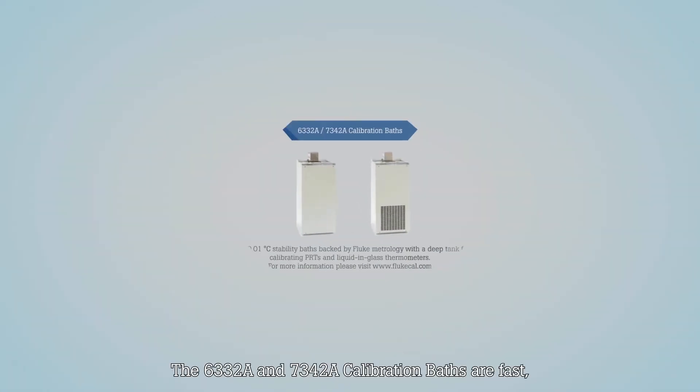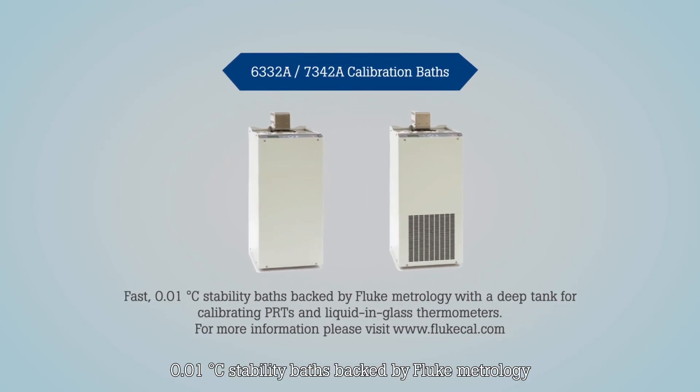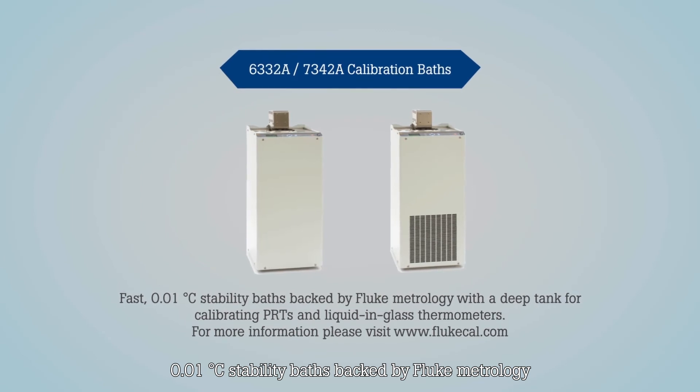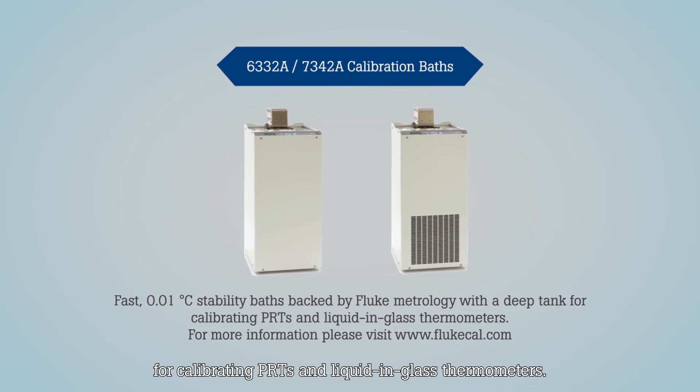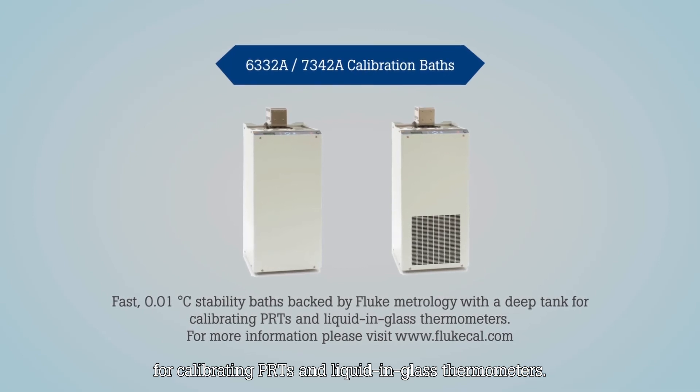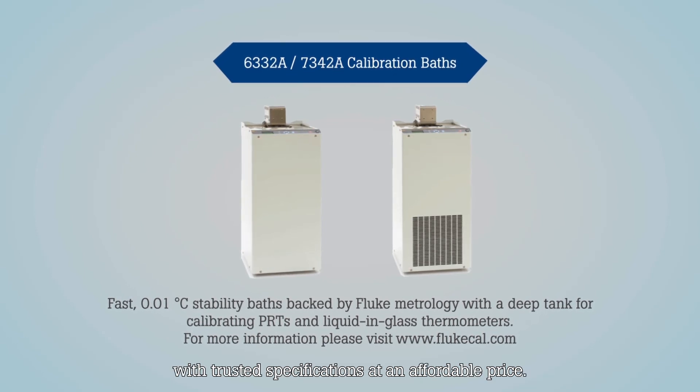The 6332 and 7342 calibration baths are fast 0.01 degree Celsius stability baths backed by Fluke Metrology for calibrating PRTs and liquid-in-glass thermometers. They're ideal for labs that need a high-quality bath with trusted specifications at an affordable price. Please visit our website for more information.